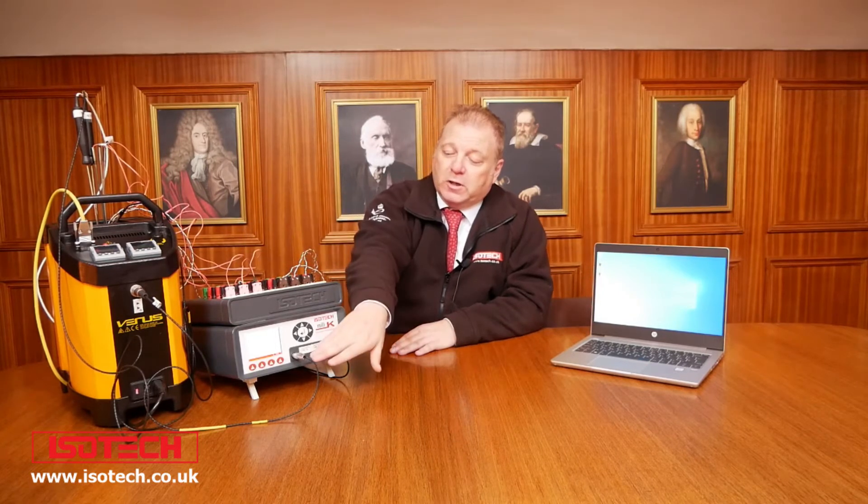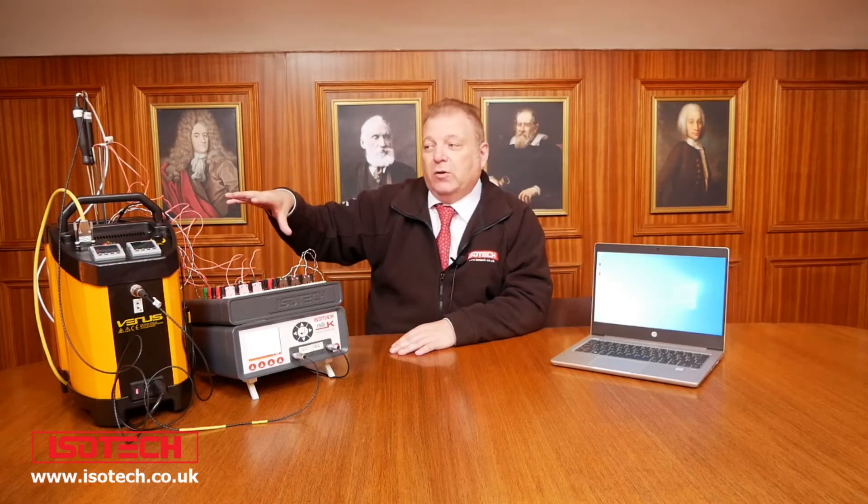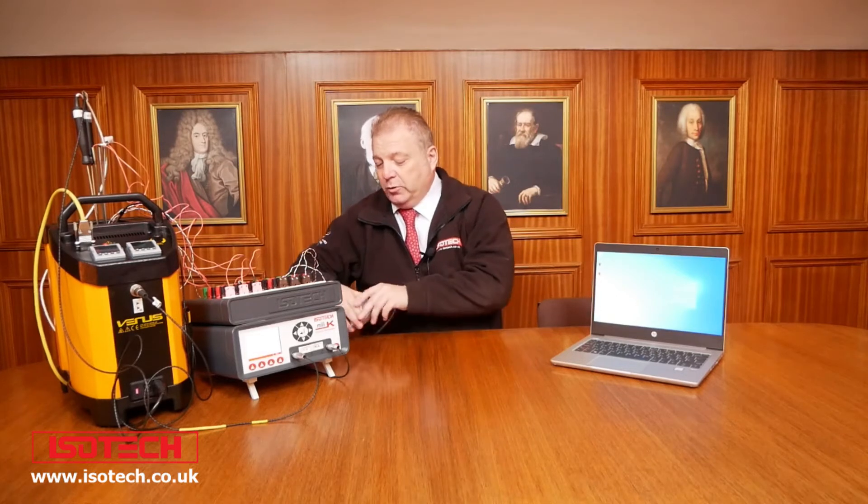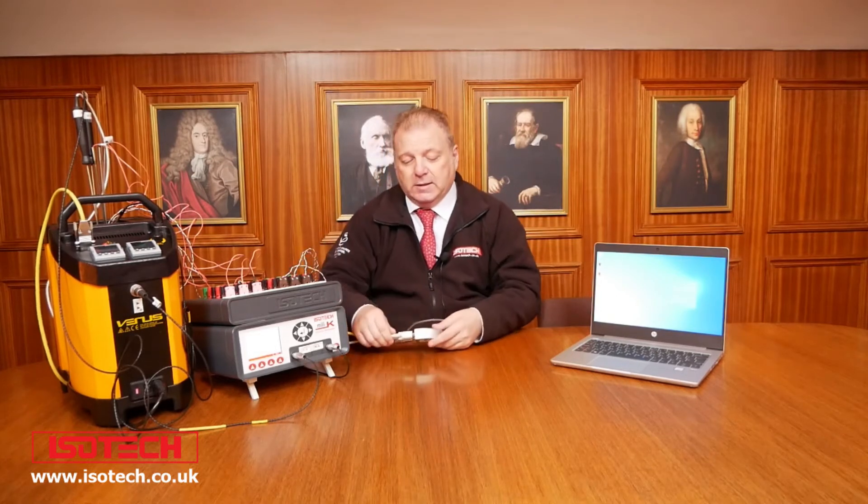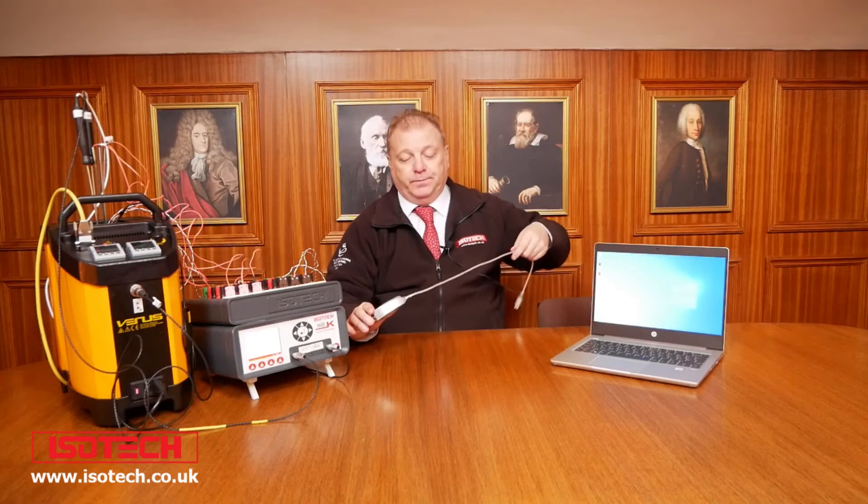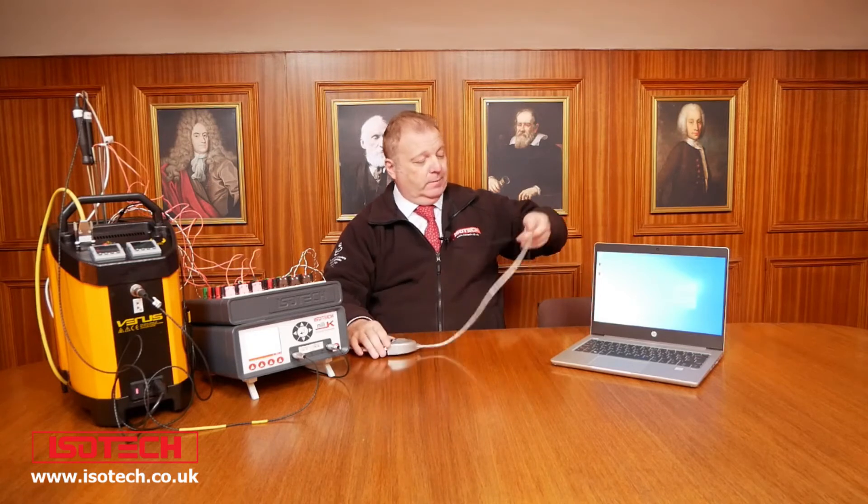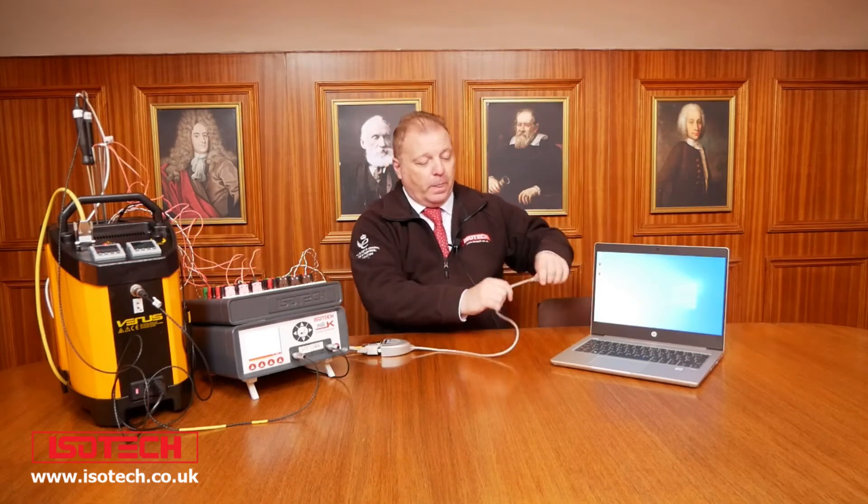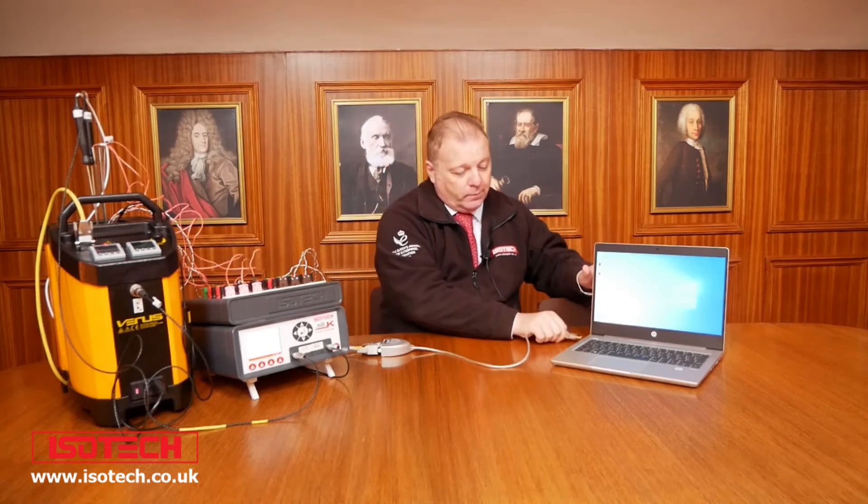We're going to use a PT100 reference here on channel one and we're going to connect all this to a laptop and run the software. To connect to the laptop, we would use a serial to USB converter and then we'll start the software.